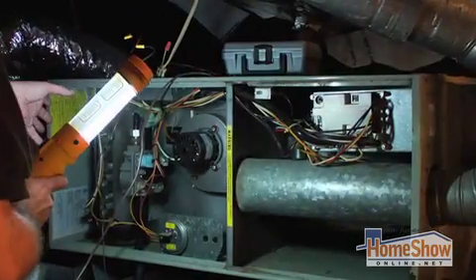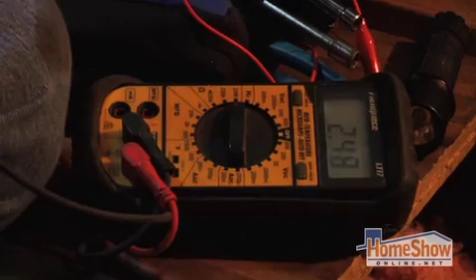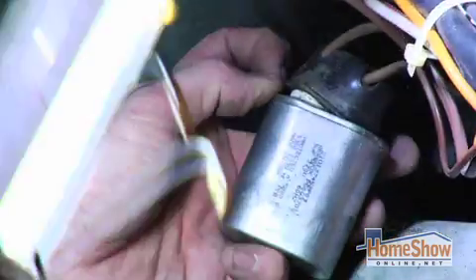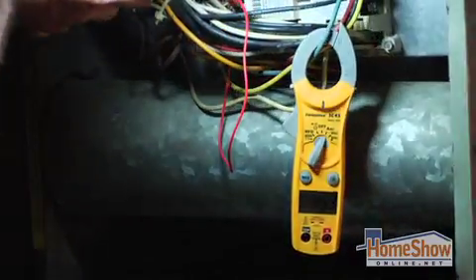Then once those are determined, we look at flue pipes to make sure they're drafting properly, and then check for flame rollouts and safety controls. We use state-of-the-art amp meters, digital volt meters, we check capacitors, we check blower motor amp draws, and we check the low voltage circuitry on the gas valve to make sure it's burning properly.